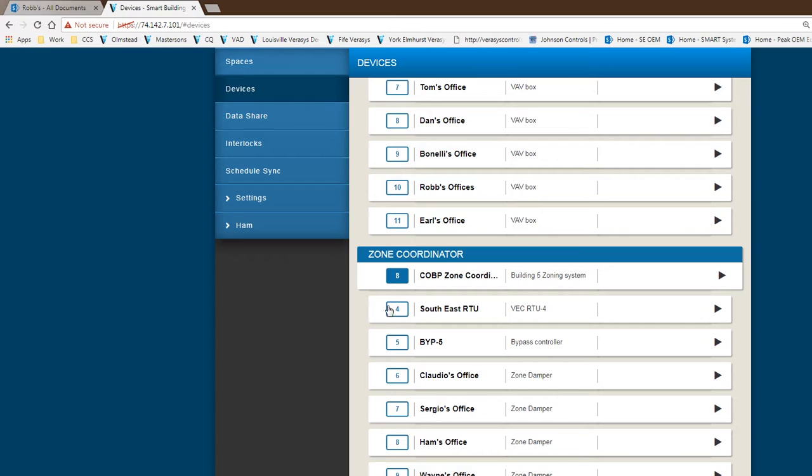One other thing to comment on: from an addressing scheme perspective, we don't have any rules in place. I address these easily, starting from 4. You really want to start from 4 and not go below it, because there are reserved addresses that we don't want to mess with, like 0, 1, 2, and 3.